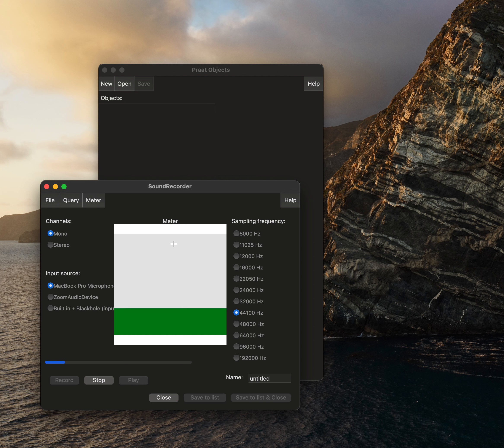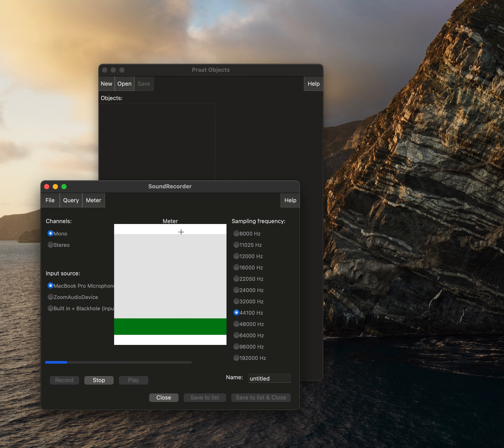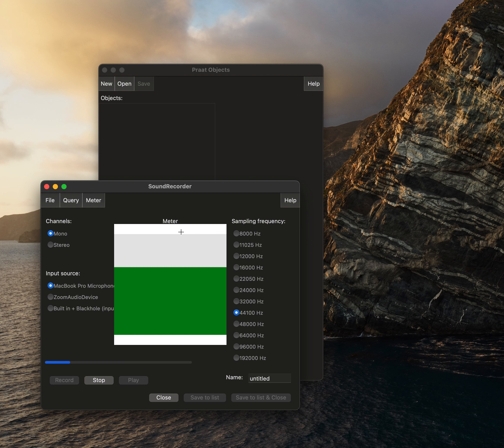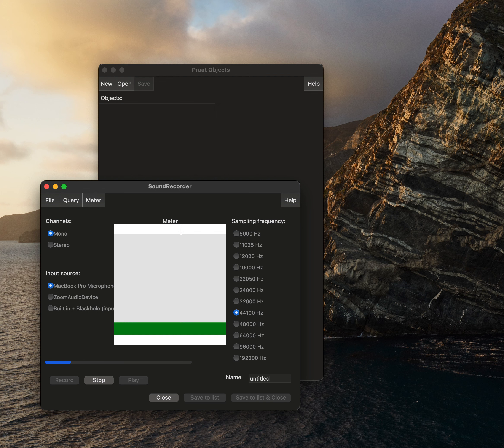If it does go into the red we're going to want to increase the distance between microphone and mouth and then repeat the soft and loud phonations to ensure that the soft phonation is detected and that the loud is not going to the red. So I'll produce a loud ah that's about twice as loud as my normal speaking volume. So there we saw it in the top of the green sometimes going to the yellow. This is a good distance.